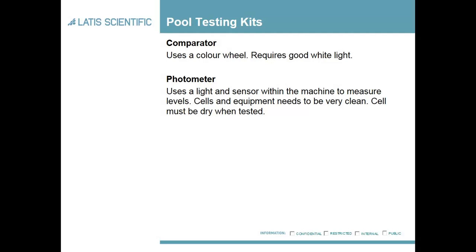A photometer uses a light within the machine at a controlled level. These need extremely clean cells — any scratches, residues, or marks on the cells will affect the extraction or absorption of the light. You can actually get a skewed reading because your standard cell will give a baseline, whereas the ones you're using with the DPD or reagent will have residue in them.